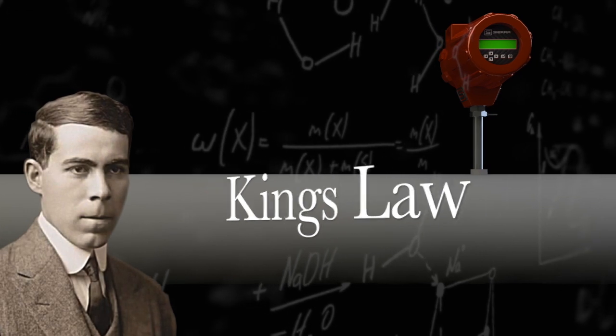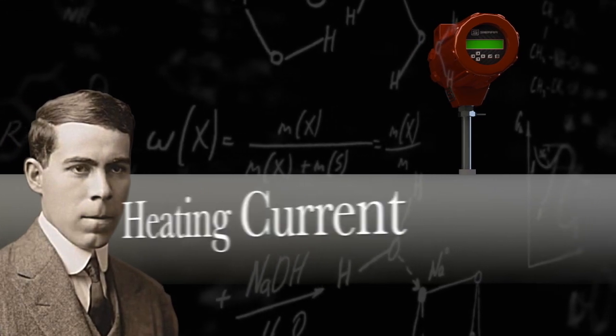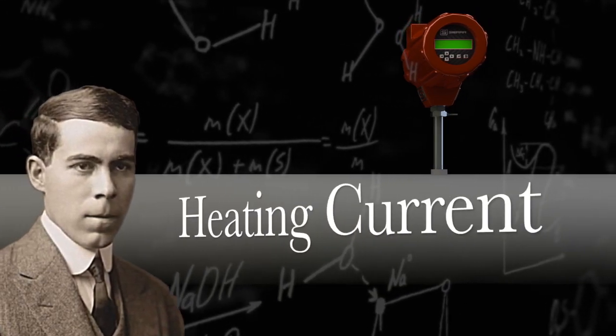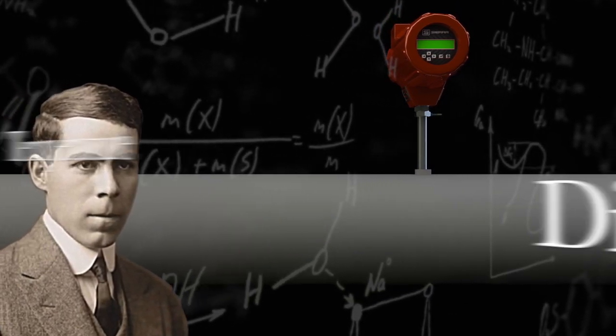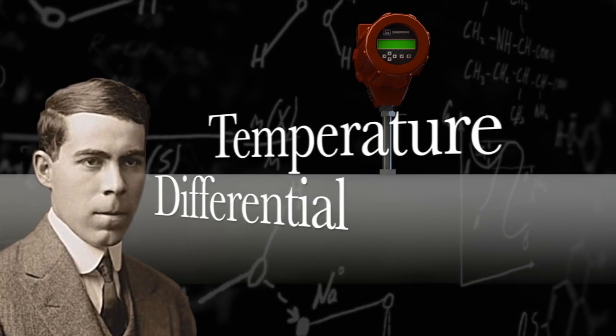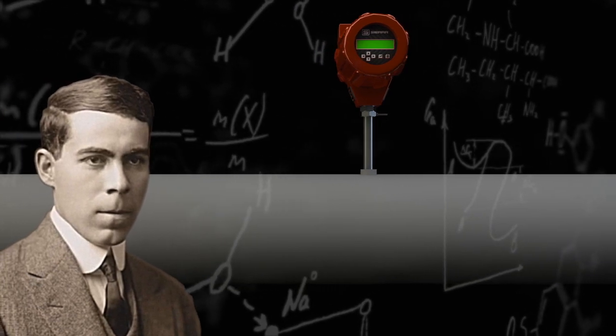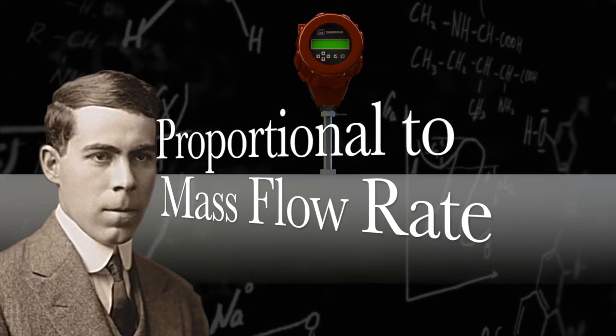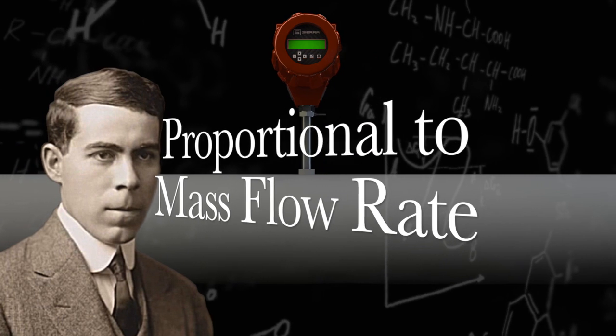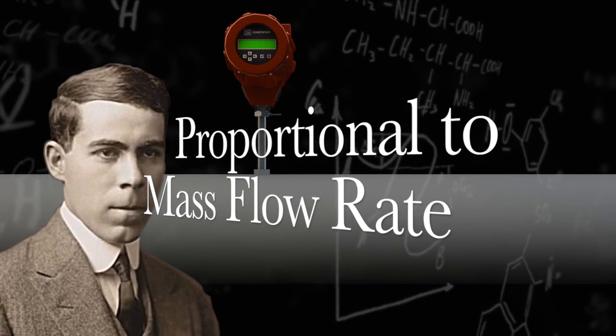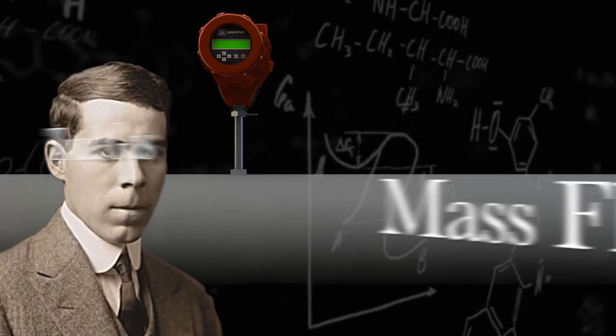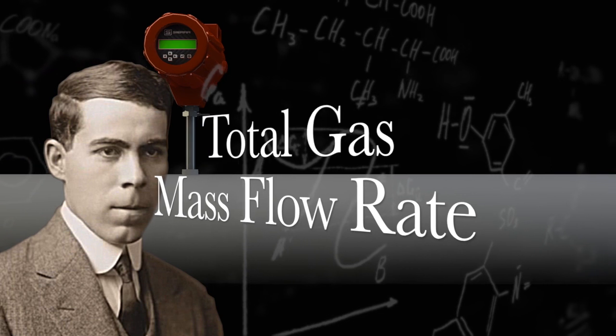As described by King's Law, it turns out that the heating current required to maintain the constant temperature differential between the two sensors is proportional to the cooling effect caused by the gas molecules flowing by, and therefore is a direct measurement of total gas mass flow rate in the pipe.